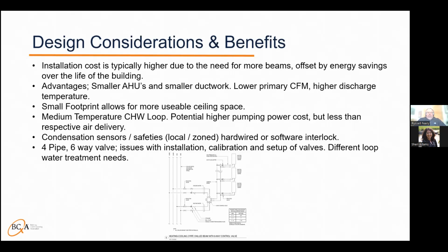And then one of the design considerations that's a must is condensation sensors. So those safeties can either be local or zoned. We've had it before where it is tied to each beam and the power for the chill water valve runs through that condensate sensor. Or it could be zoned, where maybe a quarter of a building is all looking towards a dew point sensor, and there's a software interlock or a hardwired interlock to a control valve for that zone, so that if we get to that dew point temperature, it closes the valve off.